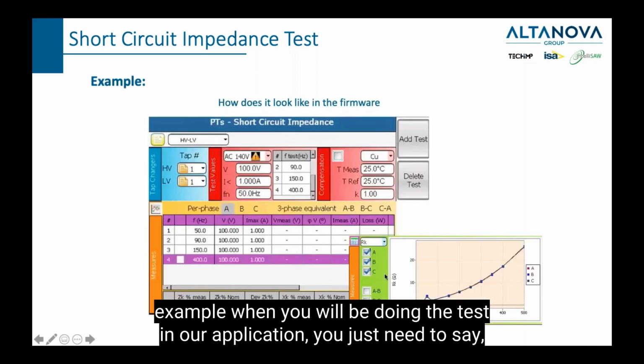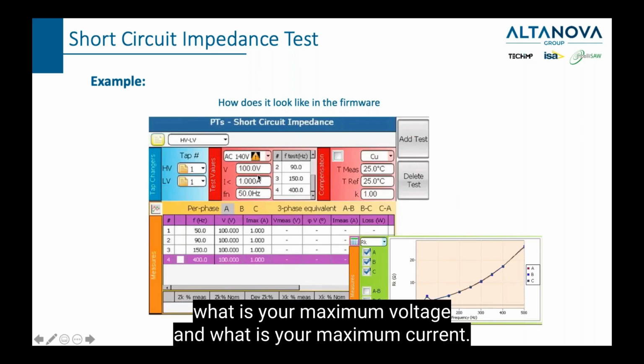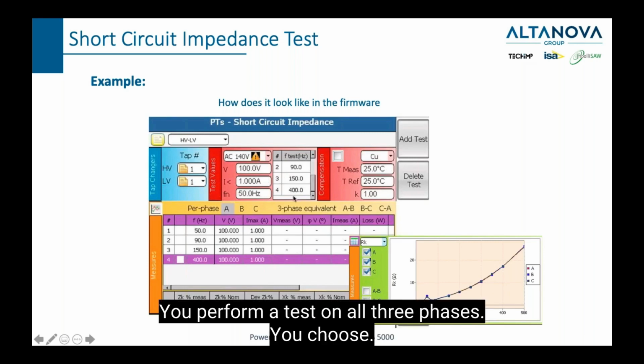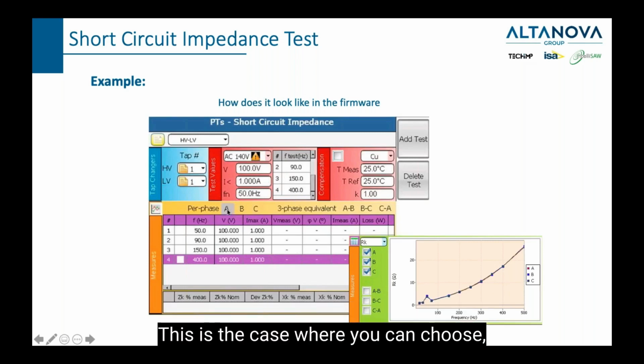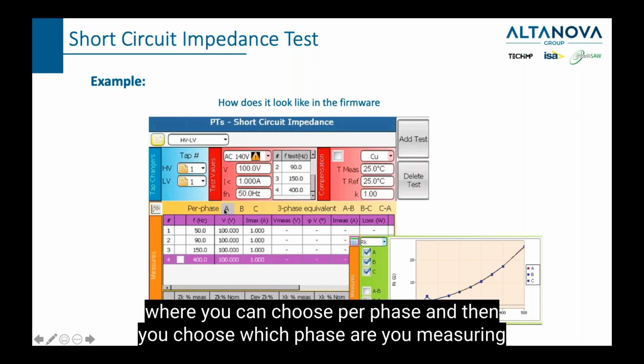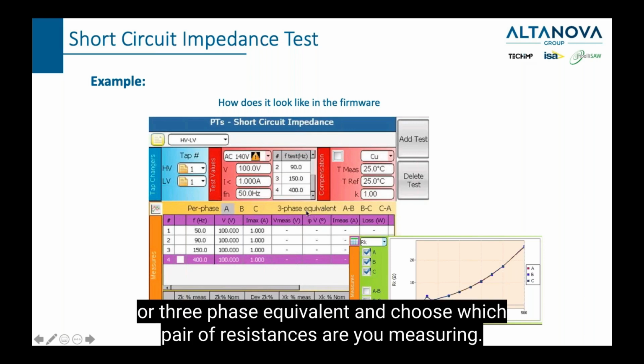When you are doing the test in our application, you just need to say what your maximum voltage is and what your maximum current is. You perform the test on all three phases. You choose per phase, and then you choose which phase you are measuring, or three-phase equivalent, and you choose which pair of resistances you are measuring.